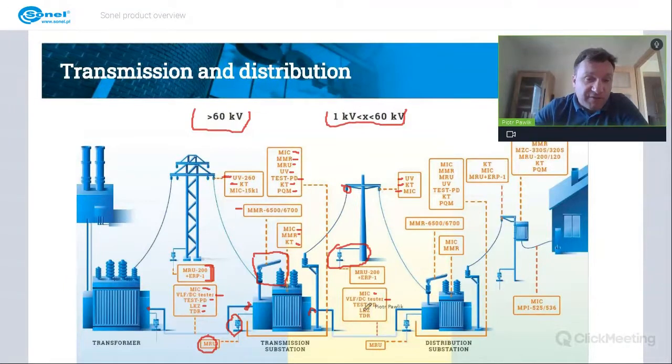We can check for partial discharges, especially at the terminations of the cables, as well as on any connectors or muffs. So that's the test PD meter. And in case we want to trace the cable and make sure that there are no damages inside them, we can use LKZ locators or TDR, the time domain reflectometer.